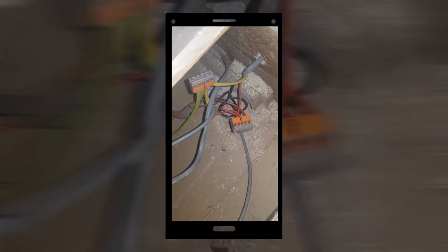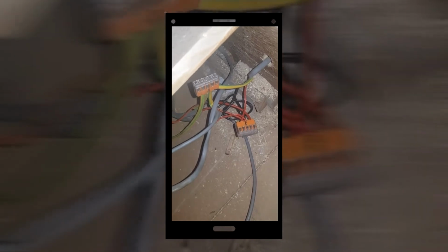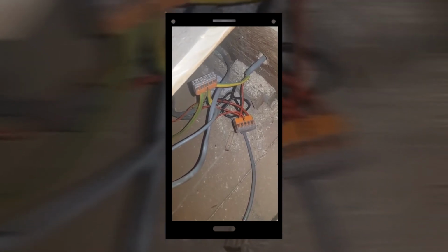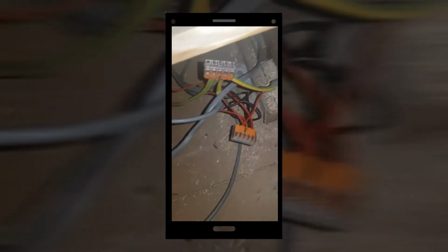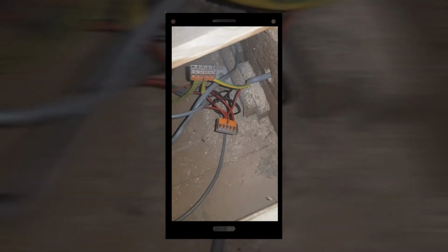So it's time to do some proper testing and find out what's going on. After a bit of investigation, I found where the touching wires were. No drama, fixed it, and decided to use these Wago style maintenance free connectors. Not a fan of junction boxes because they do work loose, really don't like them, but these Wagos are absolutely excellent, maintenance free, 32 amps. Now what's left is to tidy up, test up and do an R1 plus R2 test.